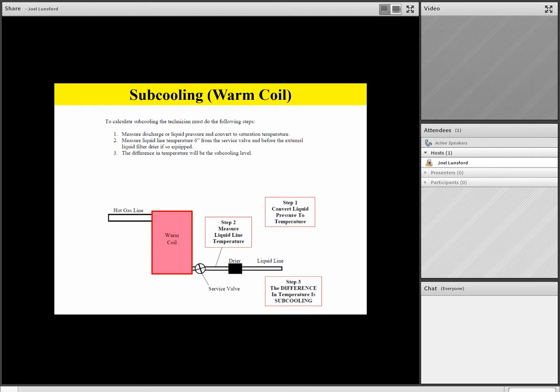If the subcooling is high, the coil is flooded. If the subcooling is low, the coil is starved. If the subcooling is about 10 to 15 degrees in the cooling mode, we'll consider that normal. If the subcooling is about 15 to 25 degrees in the heating mode, we'll consider that normal. Now remember, team, subcooling tells us the condition of the warm coil, flooded, starved, or normal. If the subcooling is high, the coil is flooded full of liquid. If the subcooling is low, the coil is empty of liquid. If the subcooling in the cooling mode is about 10 to 15 degrees, we'll consider that normal. If the subcooling is about 15 to 25 degrees in the heating mode, we'll consider that normal.